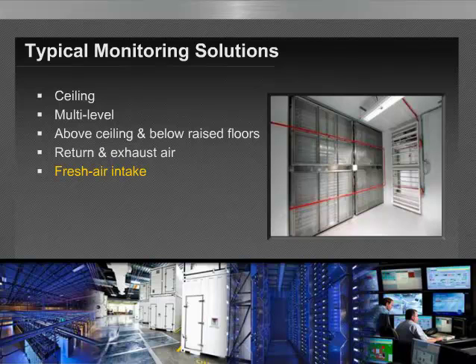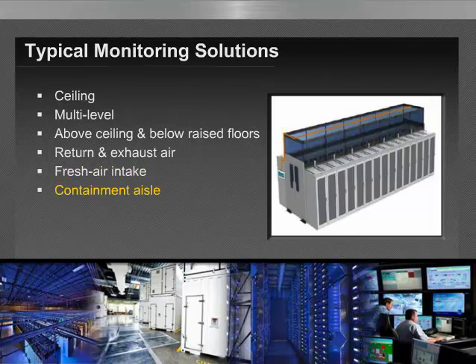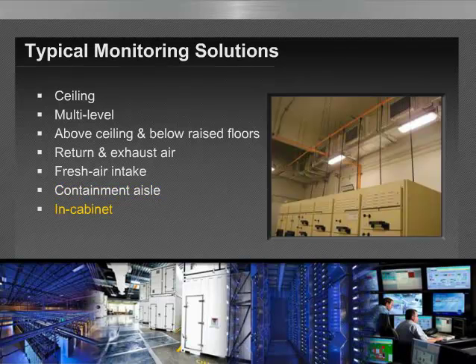And as well, the idea of monitoring containment aisles, the idea of placing the sample pipe at the exhaust path of the containment aisle to detect smoke coming from the racks themselves. And within cabinets, as we've touched on, the idea of bringing the sampling to partially or fully enclosed cabinets to monitor within the source.